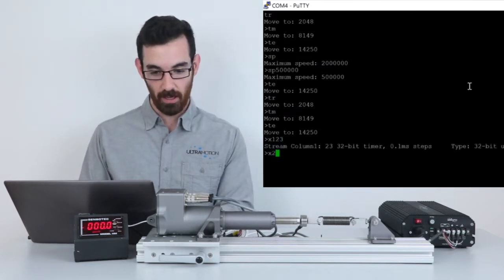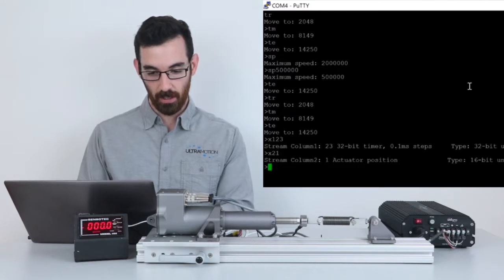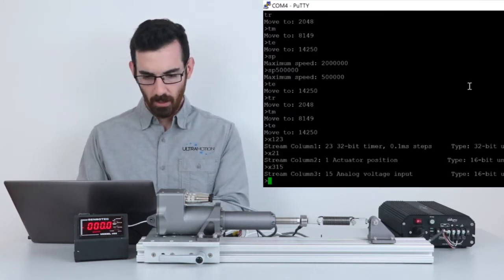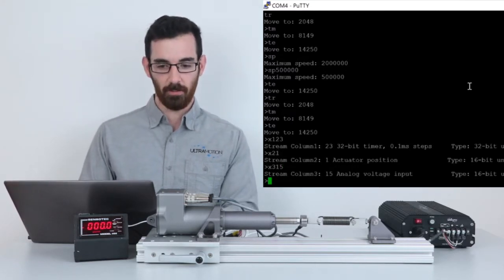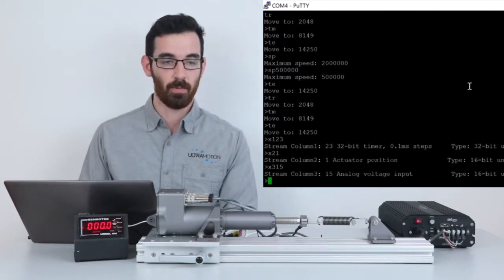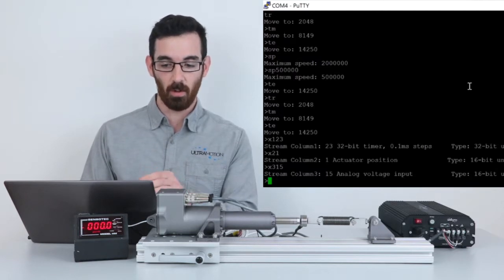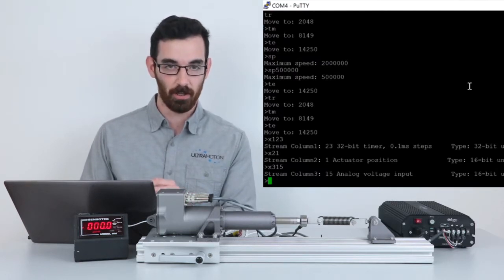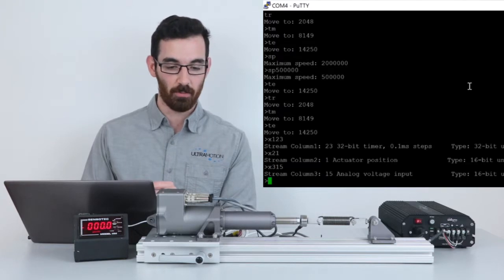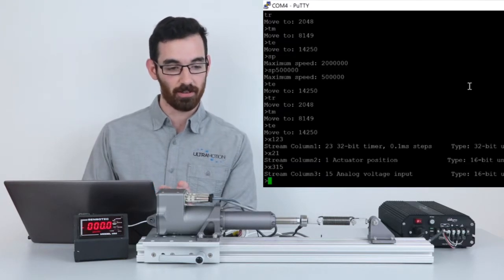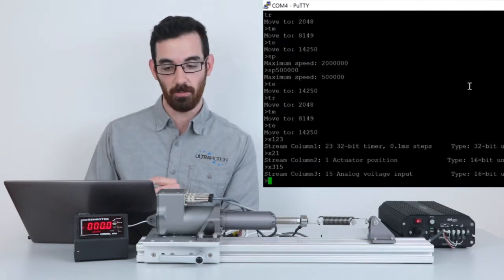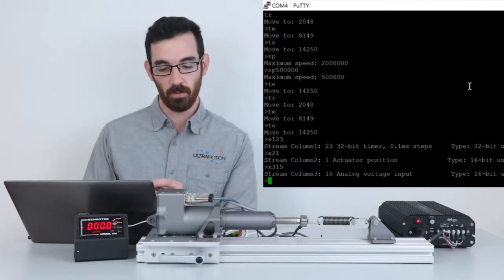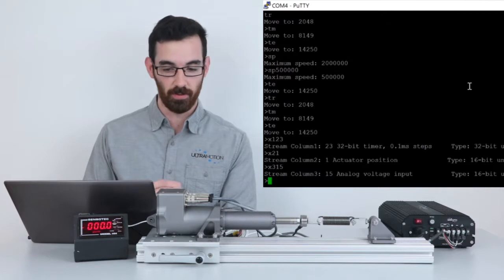I'll set the streaming constant setup to read the 0.1 millisecond timer on the actuator, the actuator's position as defined by the phase index absolute position feedback, and the analog voltage input which is coupled to the load cell.